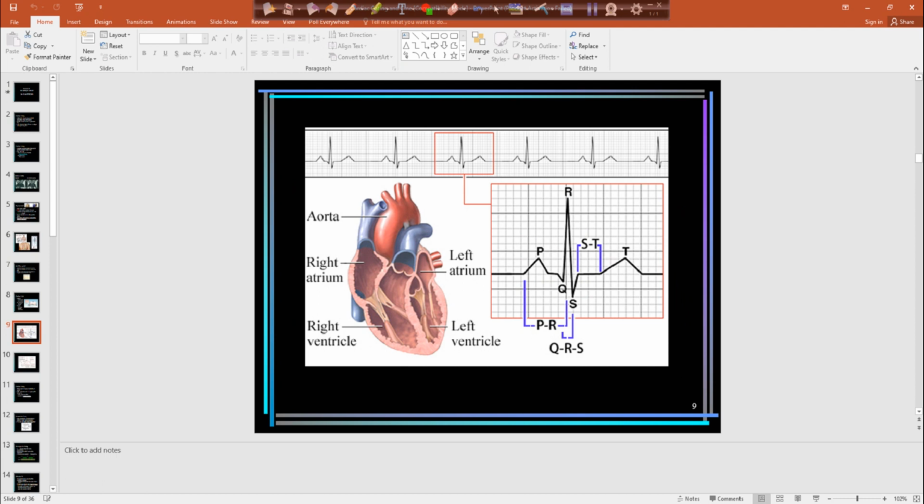So this is just kind of a breakdown of what it normally should look like. P wave, QRS, and then our T wave a little bit later on. So you can see here, we do not want to be imaging during this time right here.